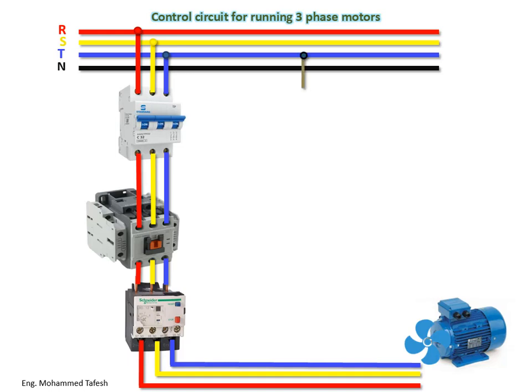Having shown the power circuit, we now move to the control circuit. The control circuit consists of a single phase and neutral only. We take a point from any of the phases because the goal of the control circuit is to send an electrical signal to control components such as contactors. Through the contacts, the power circuit is turned on or off as needed. A fuse or small circuit breaker for the control circuit — rated at 6 amperes or 10 amperes — is used because the loads of the control circuit are magnetic coils of contactors, signal lamps, and measurement indicators.